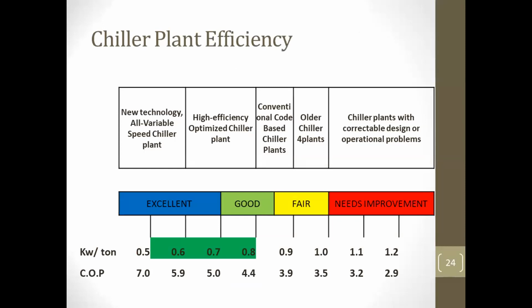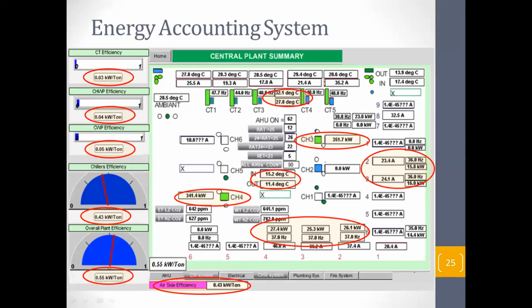And if you are more concerned about ASHRAE, this is what ASHRAE says. Overall plant efficiency, this is the water side of your system. If you want to become excellent, it has to be less than 0.7 kilowatt per ton overall plant efficiency. In one of the slides, I will show you a plant which was way above here, somewhere here, and has been brought to somewhere around here with minimum effort. And this is an illustration of how somebody has achieved it.